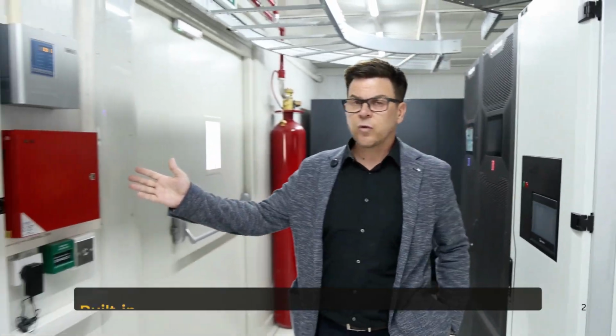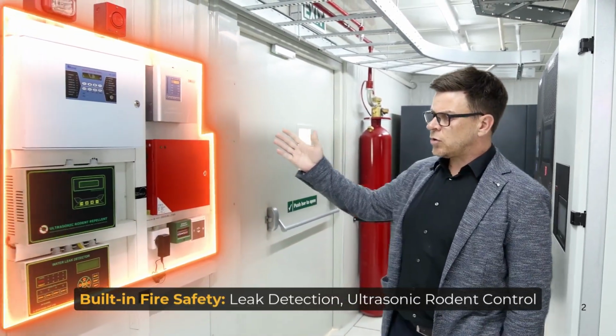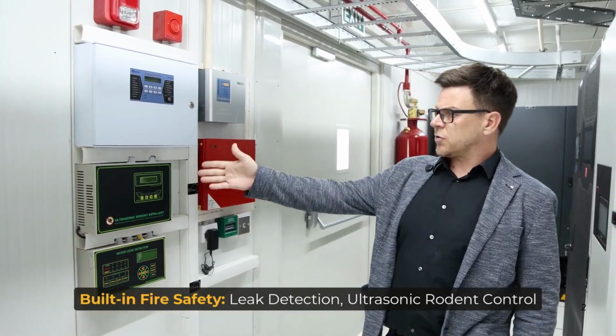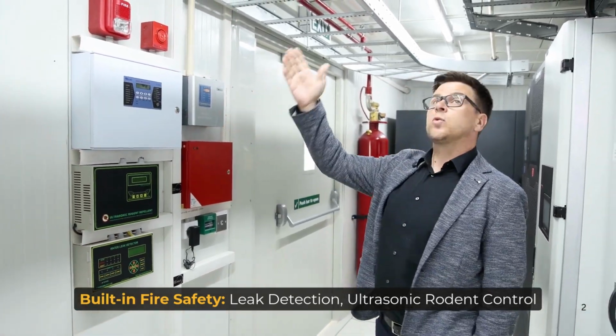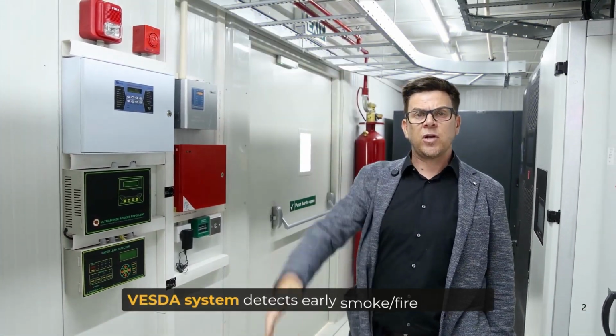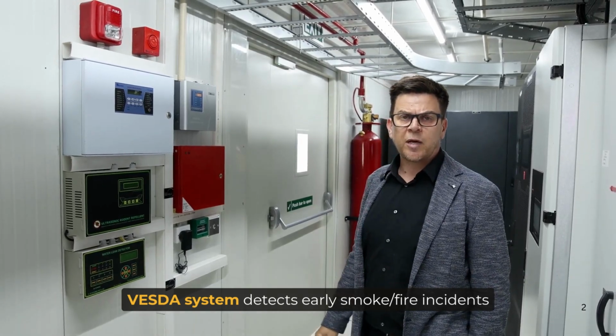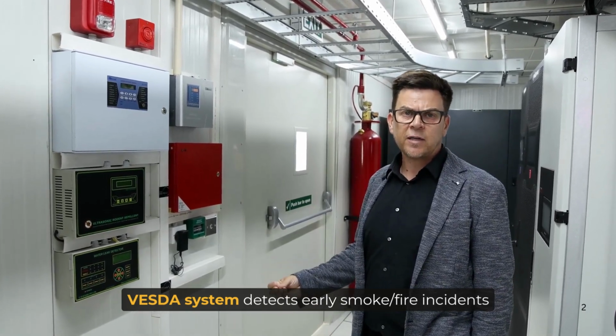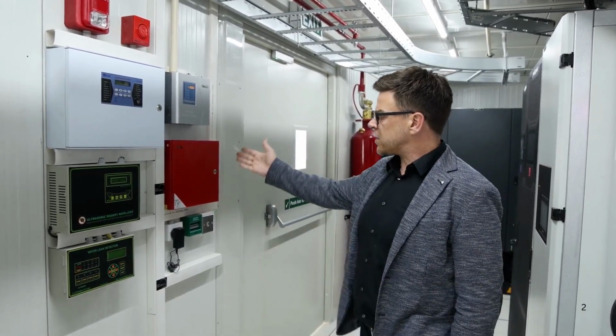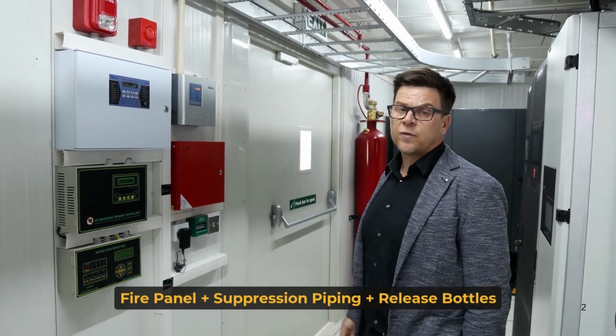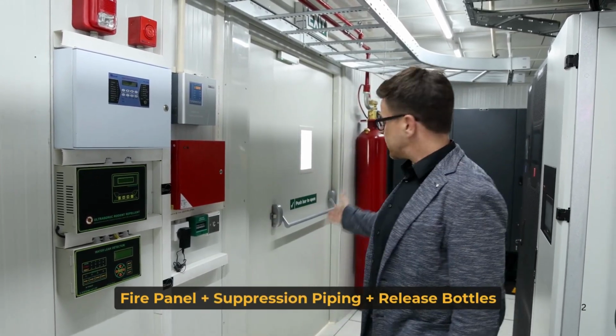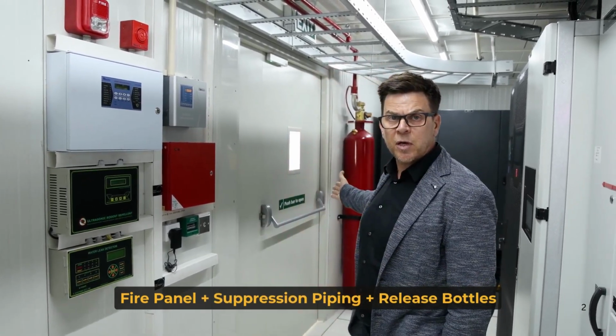On the right-hand side, we have all the fire equipment, which includes water leak detection, ultrasonic rodent agent release, and VESDA, running through the pipes, very early sampling detection, which will pick up smoke particles or any incidents of fire. This is supplemented by a fire panel with fire suppression piping, as well as the fire suppression module that you see behind me over there.